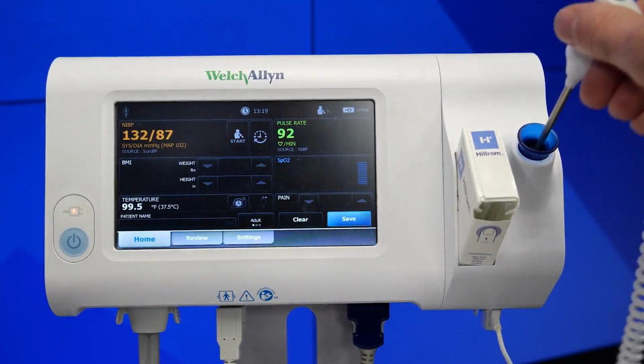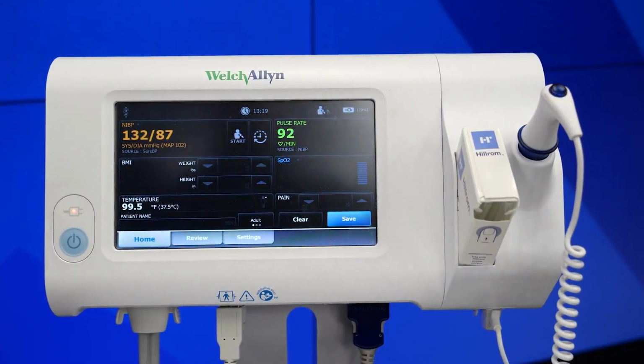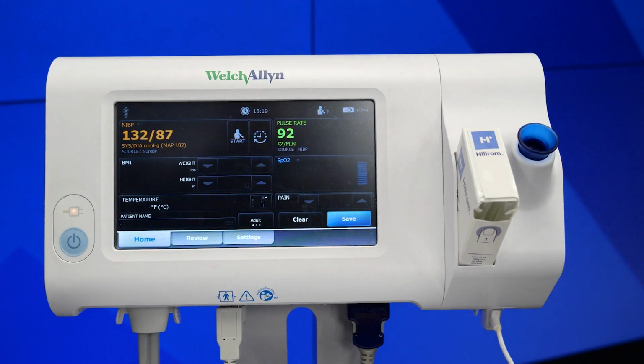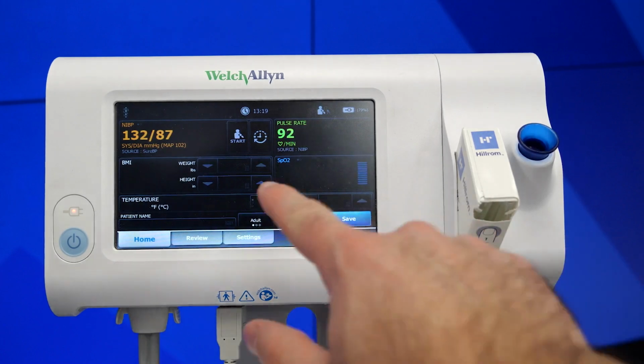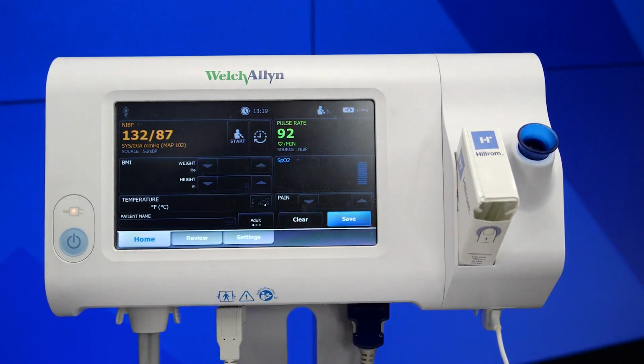The SureTemp Plus technology in our temperature probe contains a preheated filament that reduces the time to take a reading by bringing the probe to body temperature prior to measurement. The SureTemp thermometer can also be used to obtain axillary and rectal temperatures. For rectal temperature measurements, a different probe and probe well is required. To switch between these measurement methods, there is an icon within the temperature tile.